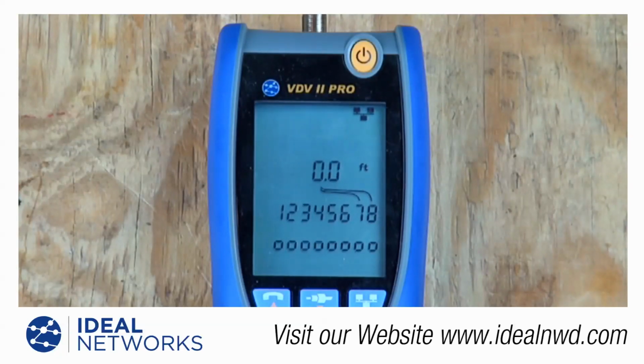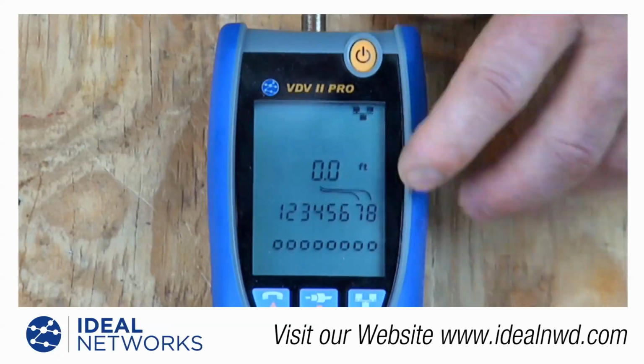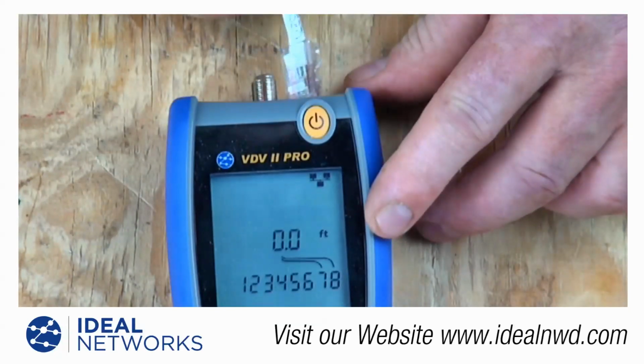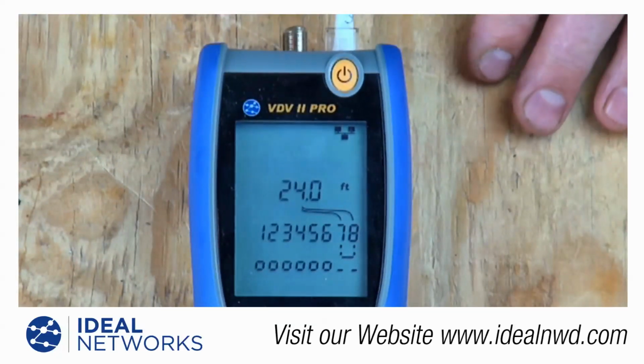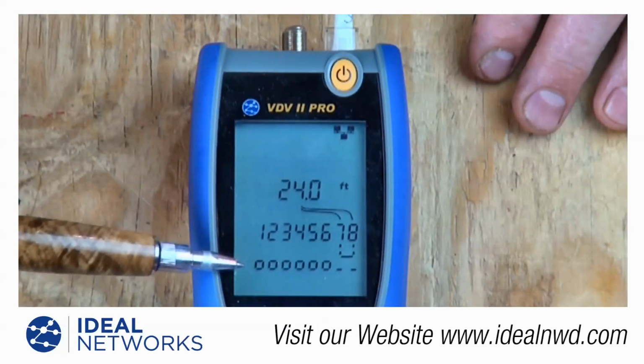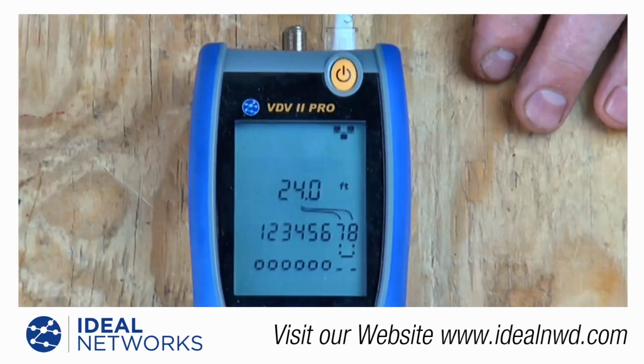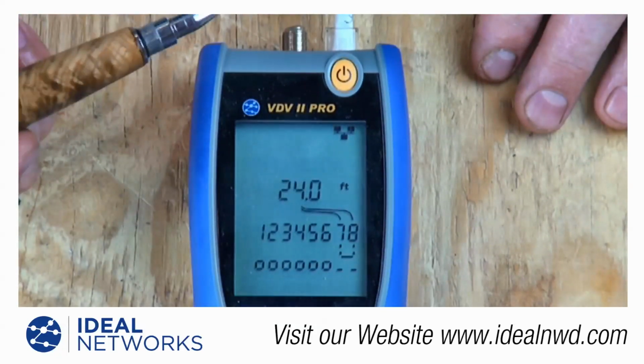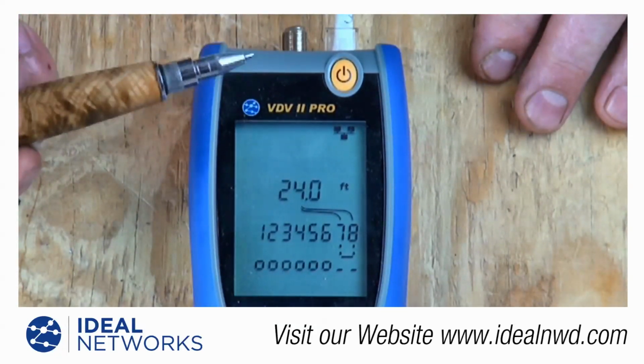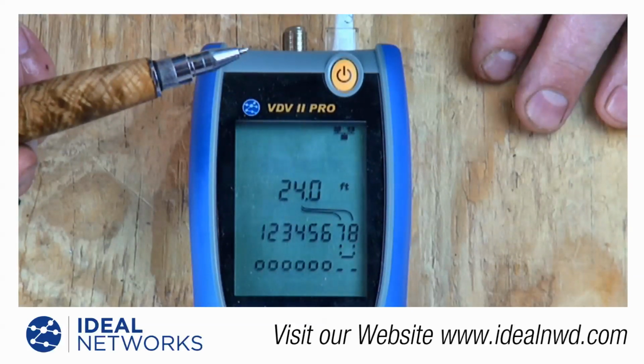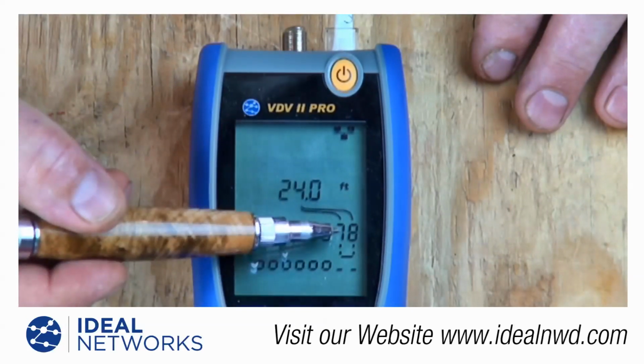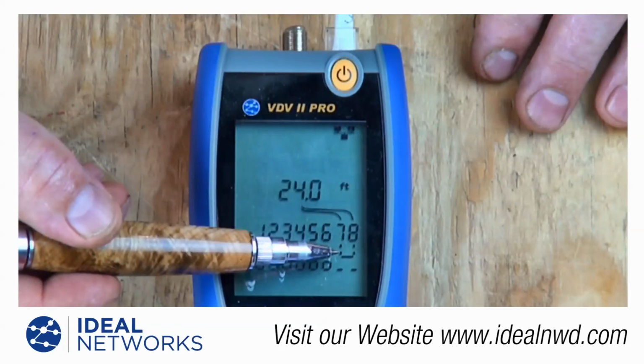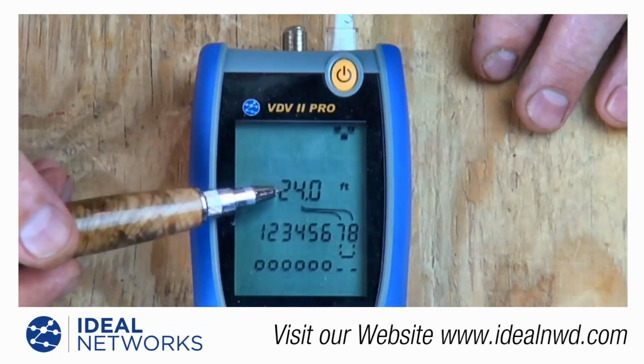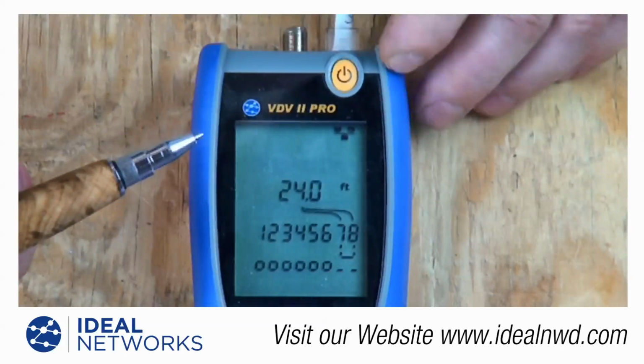Now I'm going to take another length of cable that has no connector plugged into the other end of the cable at all, and I'm going to plug that other length of cable into the top of the tester. And it's showing me that it doesn't see a remote on the other end because everything's open, because the other end of the cable is completely open. But again, showing you some of the features of the TDR function of the tester. We can get you distances to opens or distances to a short. Now in this case, pins 7 and 8 are shorted by that little icon. That icon indicates that it's shorted, and it's about 24 foot out in the length of the cable.